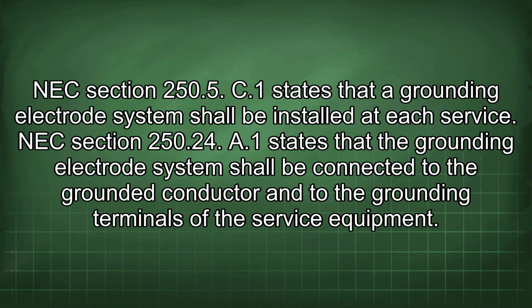NEC Section 250.5 C1 states that a grounding electrode system shall be installed at each service. NEC Section 250.24 A1 states that the grounding electrode system shall be connected to the grounded conductor and to the grounding terminals of the service equipment.